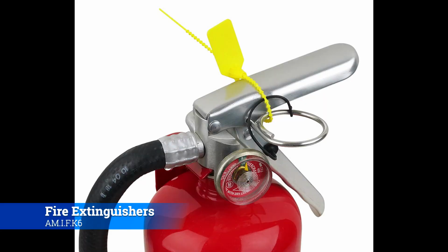Safety seals are unbroken, so you want to make sure that your fire extinguisher has the seals that have been inspected, and that it is in date, and it's not been broken or tampered with or anything else, because legally it wouldn't be valid if it's broken. And on top of that, how do you know that it's actually good if the safety seal is broken? All right. All external dust and dirt removed. Keep in mind that fire extinguishers are generally ferrous metals.